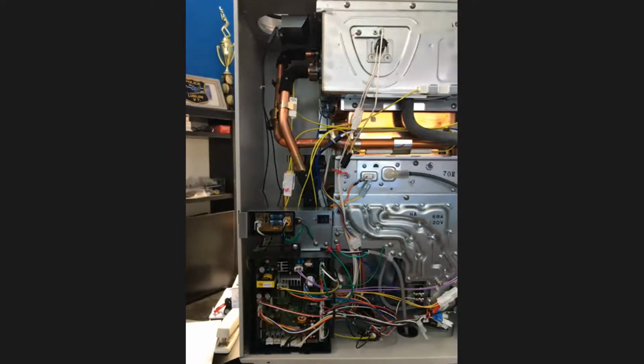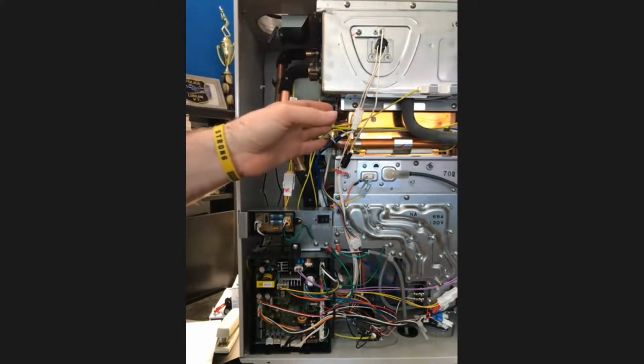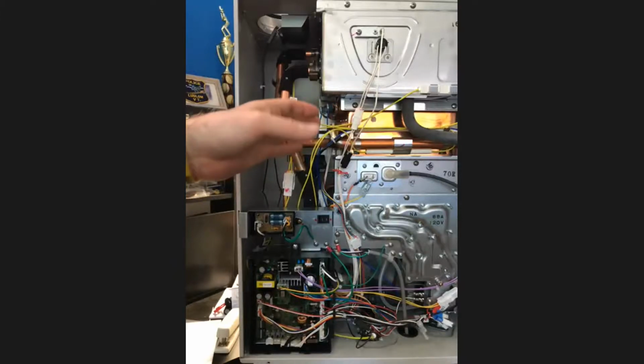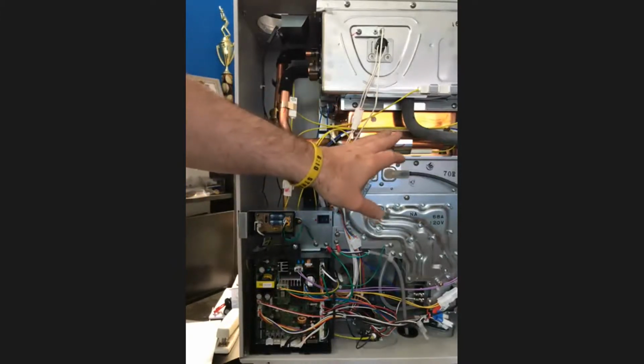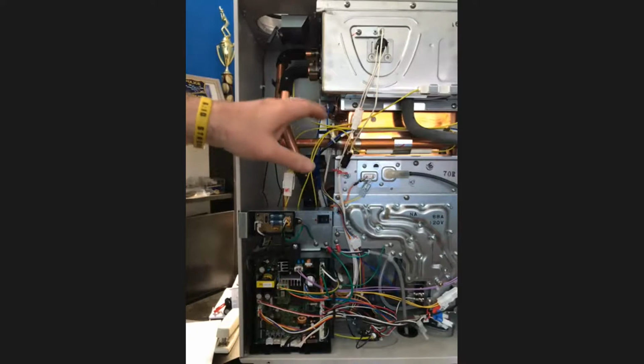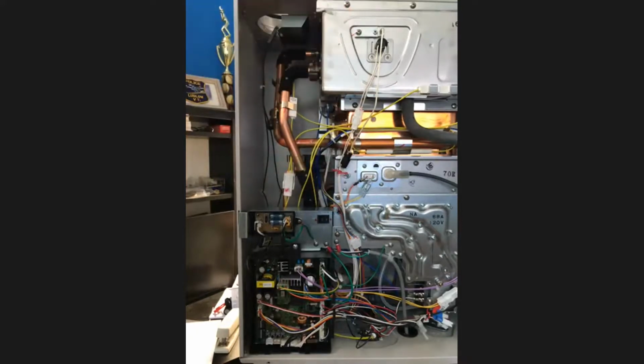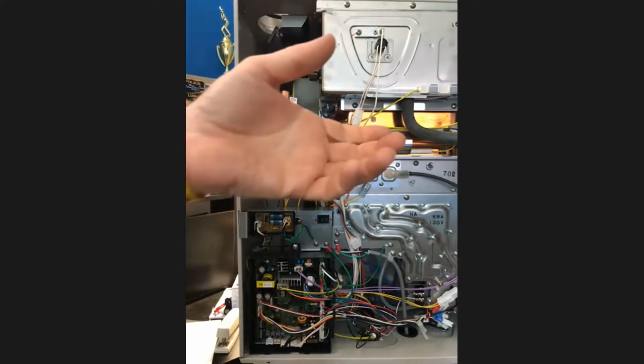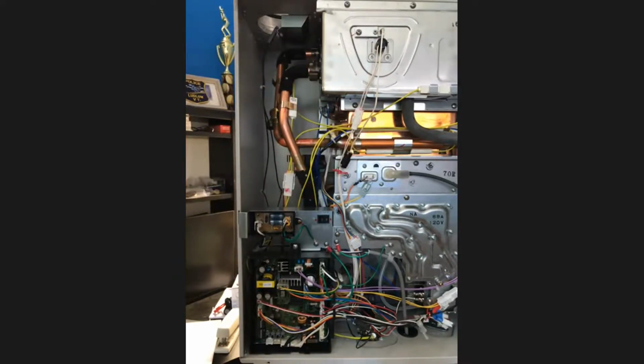Circling back to the two heat exchangers, because it's a little confusing: we go into the secondary first and the primary last. My hottest flame is here as I'm heating it up, and then when I come across here, I'm taking out that last little bit of energy. That's where I bring the flue temperatures down into the condensing range.